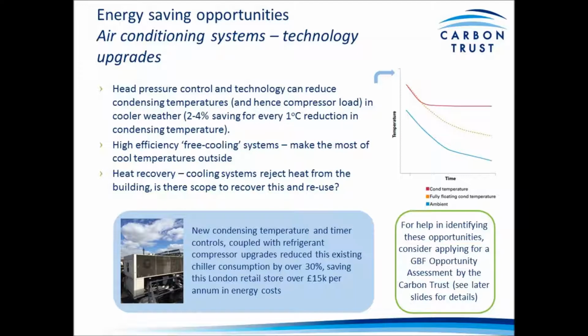In the UK, we have a climate with a high number of hours where external temperatures are cool enough for free heat rejection. So free cooling systems can often maximize the benefit of this by utilizing these external cold temperatures to reject heat without the need for temperature elevation by the compressor in the cooling system. So again, that can be one way of improving the efficiency in investing in upgrades. Another consideration is that cooling systems essentially reject heat from a building, and this low-grade heat can be recovered for use in preheating hot water, for example, so you can recover this heat that's rejected.